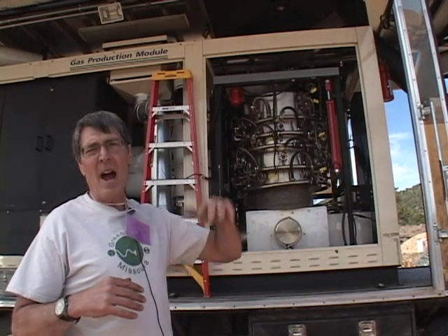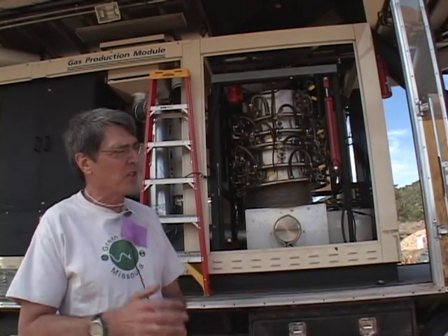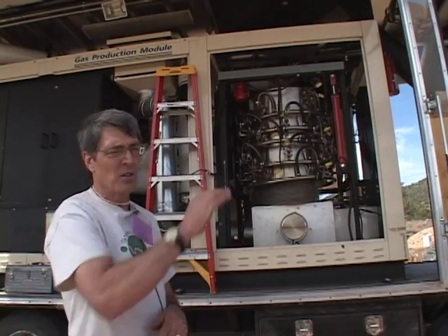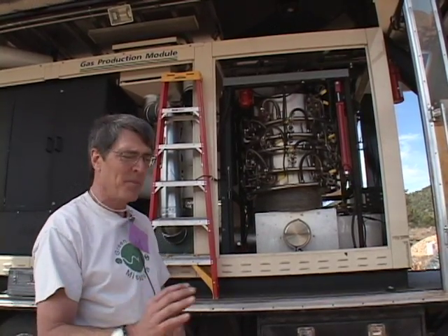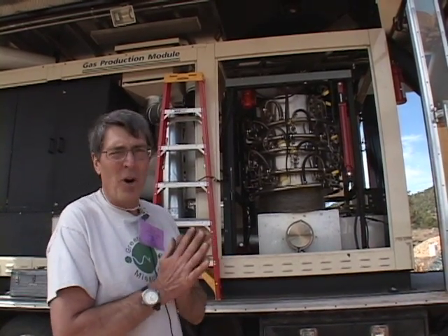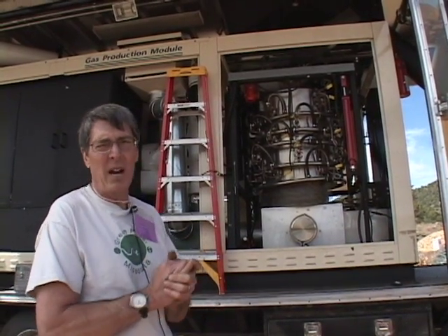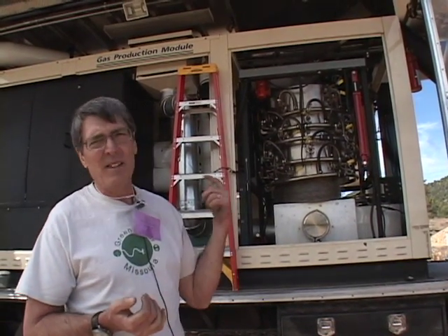There's a number of reactions that occur in a gasification process. Some are endothermic, some are exothermic, so the temperature profile through the reactor is not constant. It's high, and then it goes a little bit lower, then it comes back high again. But we exit at about 600 degrees C. That's too hot to throw into an engine, so we cool it down. The heat exchangers on the other side, we'll take a look at that in a minute. We cool it down to about 50 degrees C. Then we take that cooled gas and we filter it in this baghouse filter system.